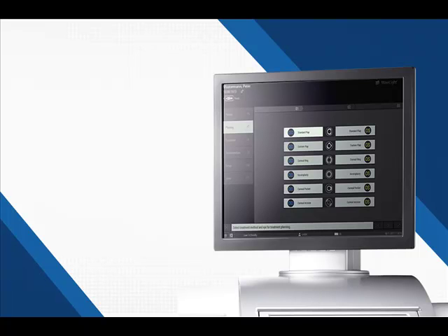So, the LenSx laser has a patient interface. The patient interface is the boundary between the laser and the eye. It's called SoftFit. SoftFit is a unique patient interface that is not based on liquid. It is partially based on liquid, but not completely. And what I mean by that, we'll get into in a bit when we look at competitive systems.